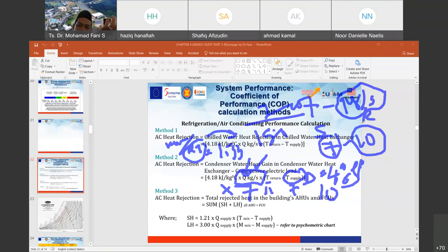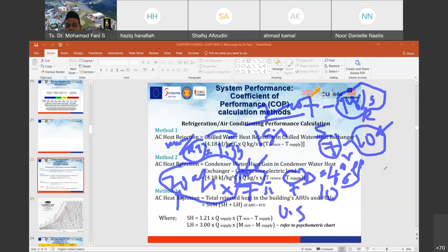If not, you need to get something like 20 kg per second. Try 20 kg per second and then try to simulate. I will ask you: what is the value of the flow rate of the chilled water that needs to be achieved by the chillers in order to get a better improvement of COP, at least 0.5? And we maintain the supply temperature and return temperature at about 7 to 10. So how much is needed to get that COP? Do a bit of math.